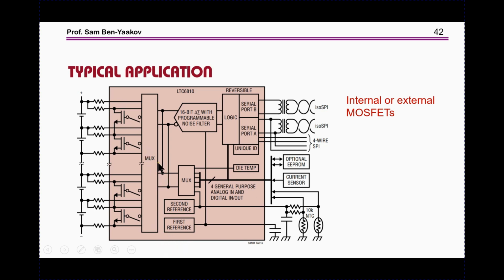Here I'm showing a Linear Technology unit where you can have either internal switches or connect an outside switch. There's the discharging resistor, monitoring, a multiplexer, A to D, and digital processing going on, with a bus that sends out the information. Each unit can accommodate up to about 12 cells, so you need quite a number of these for a high voltage battery. It's a rather involved system, but unfortunately it's a must in order to keep the battery running without faults.